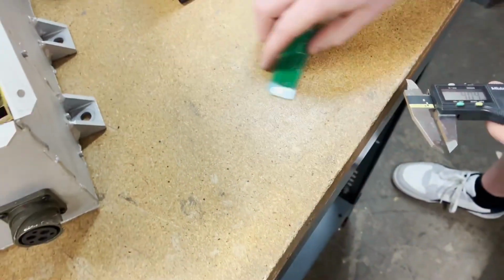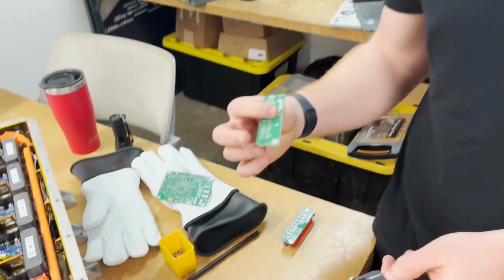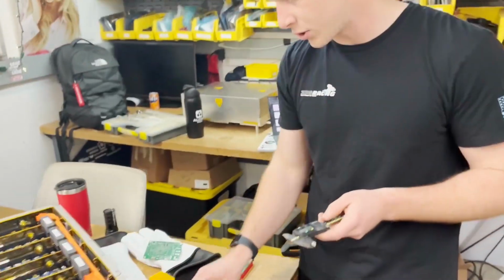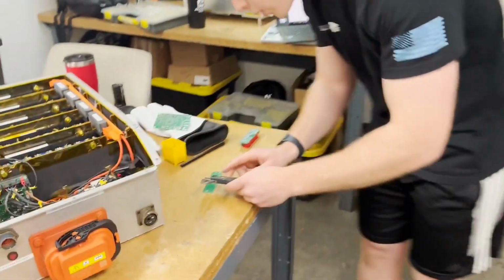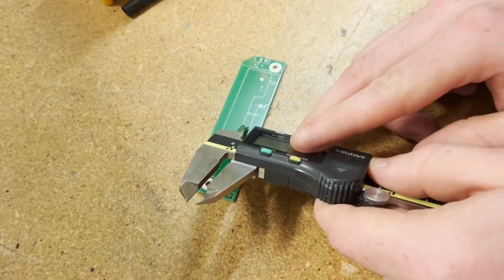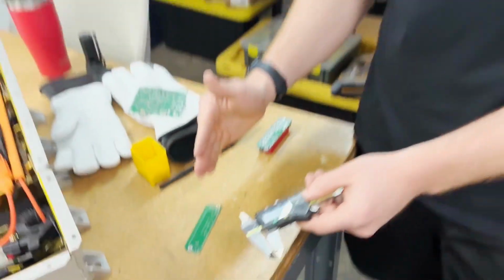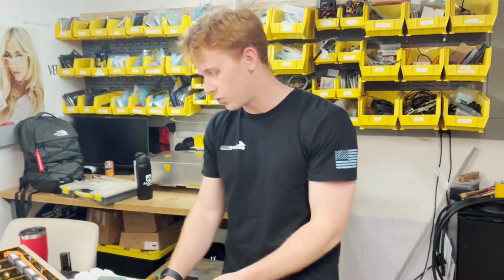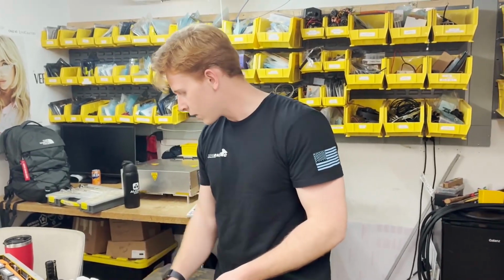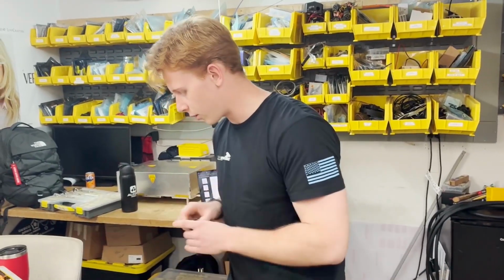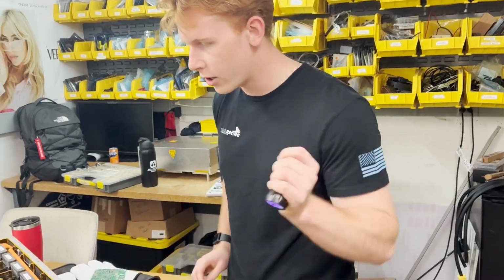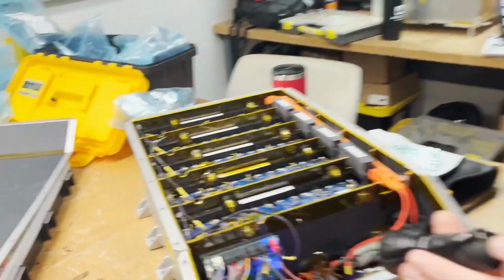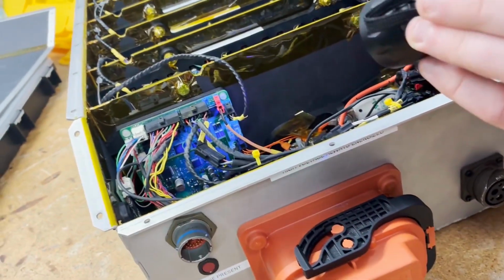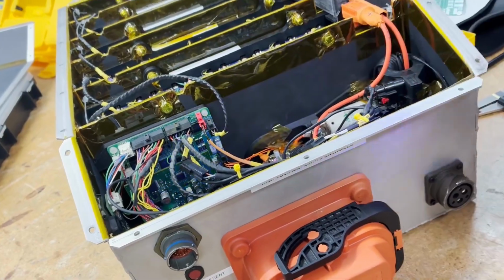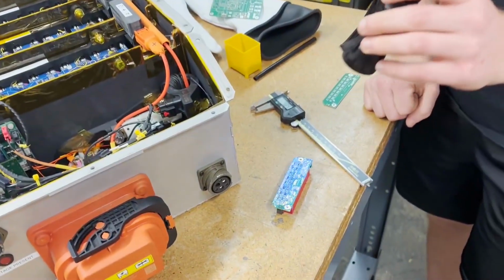We also have a high voltage discharge board that houses all of our discharge resistors. The gap here also exceeds 4 millimeters from the copper heat dissipation pours to the wiring. As for showing the conformal coating, since that distance would require it, you can see the reflective glow of the conformal coating in the battery, and likewise here on our discharge PCB.